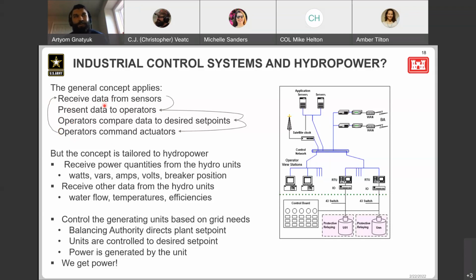So we tailor this concept to hydropower. Instead of just generic data, we actually receive power quantities from the hydro units - this could be real power like watts, or imaginary power like VARs, amps, volts, breaker position, and other indications the operator might need for control of their hydro units. We also receive other data from the hydro units, like water flow coming out of the unit, temperatures, and maybe efficiencies we want to grab to see how efficiently the unit is operating or generating megawatts.